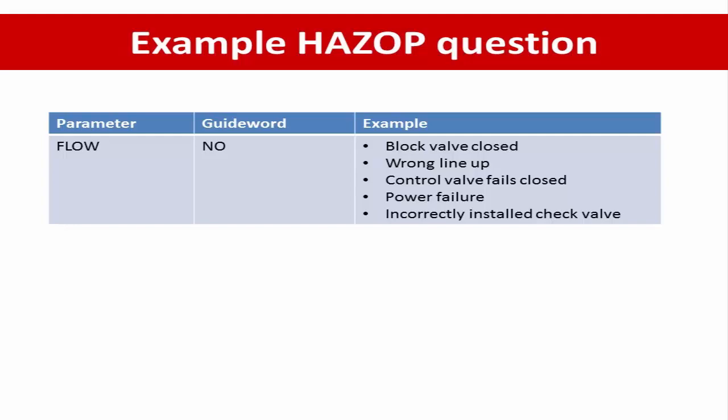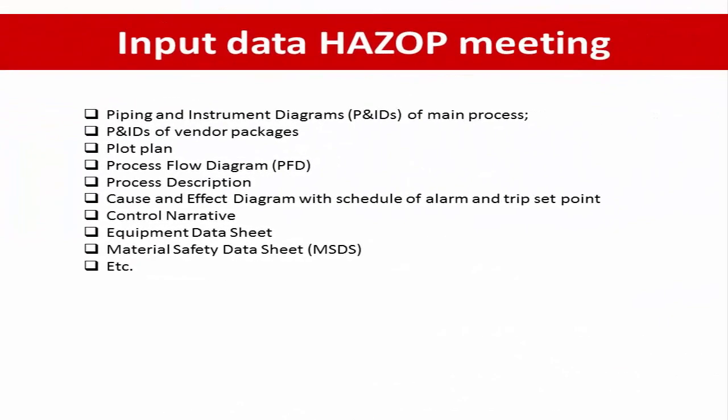Input data to be prepared for the HAZOP meeting: the most important document is the Piping and Instrument Diagram for the main process or for the vendor package. Other inputs include the plot plan, process flow diagram, process description, cause and effect diagram with schedule of alarm and trip set points, control narrative, equipment data sheet, and material safety data sheet. These are the most used information during the HAZOP meeting.